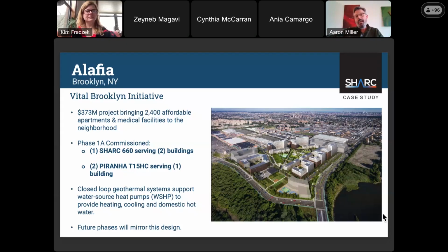And as the climate warms and the load profiles of these buildings change, you tend to see those fields drift out of the optimal temperature range. Not a problem. We use the sanitary flow from the SHARC to temper that loop, pushing and pulling energy in and out as needed. So over 10, 15, 20 years, you don't have to recommission, dig more holes, or add a cooling tower. You just use the sanitary flow the building is already making to keep that loop ideal.